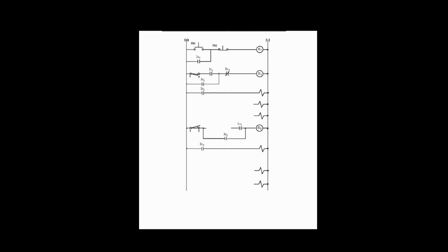Now that you know how R1 and R2 are turned on and off, let us examine the actions under the control of R1 and R2. When R1 is on, 2R1 on the template is closed. The actions under the control of R1, for example, A+, B+, C+, will be executed sequentially. Similarly, when R2 is on, 2R2 on the template is closed. The actions under the control of R2, for example, C-, B-, A-, will be executed sequentially. And the cycle continues.